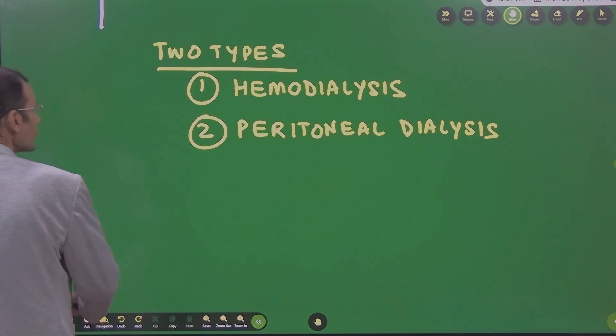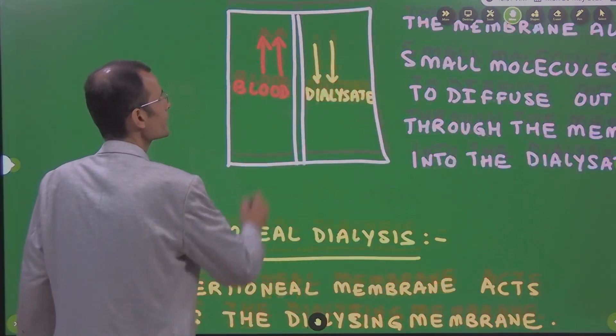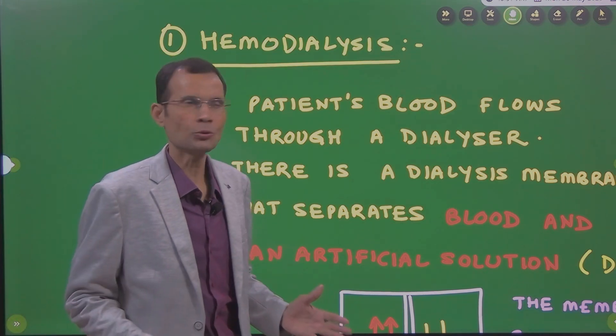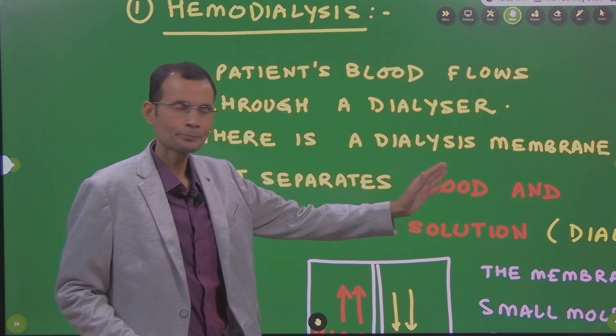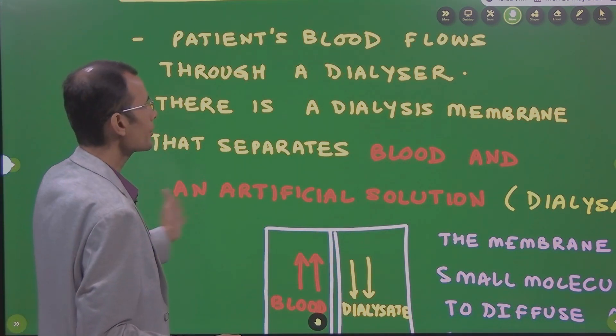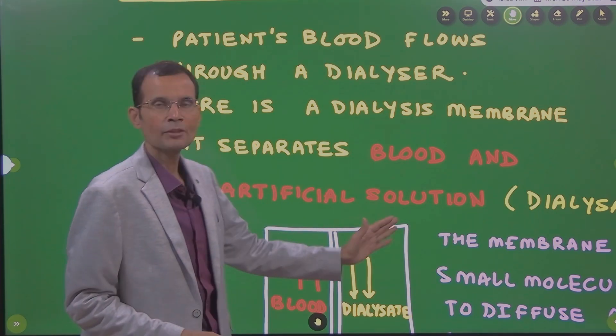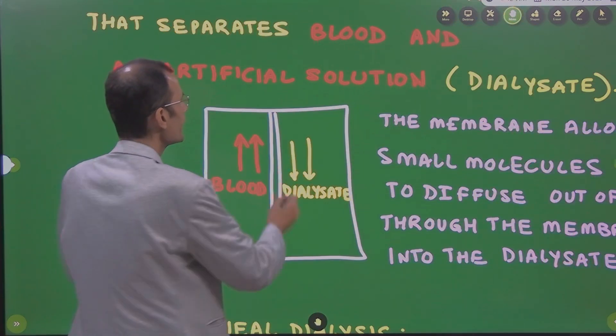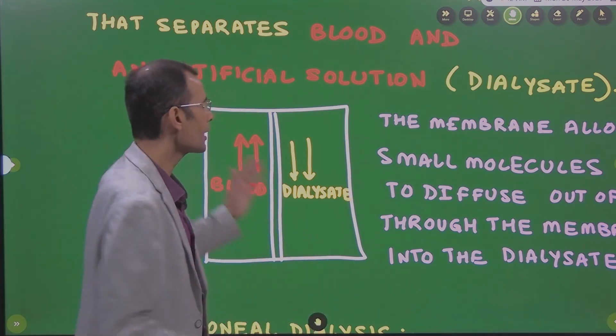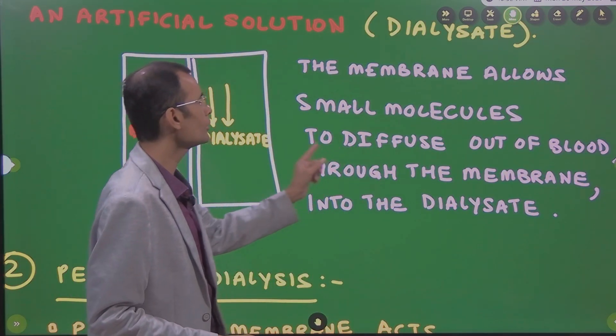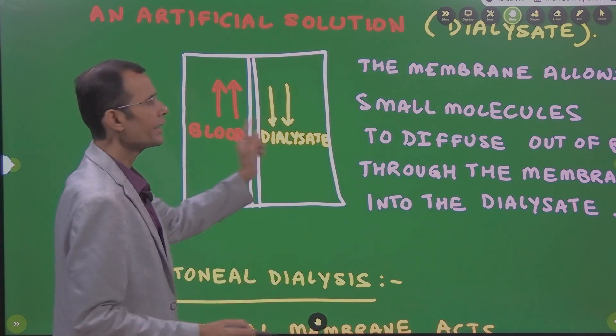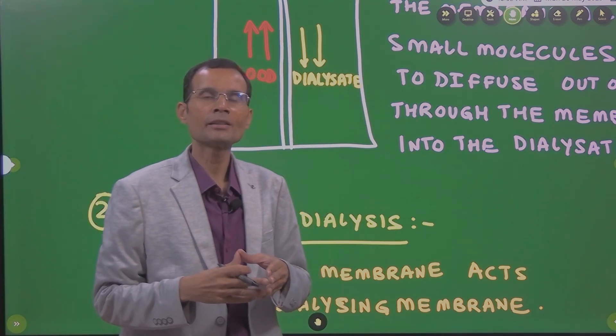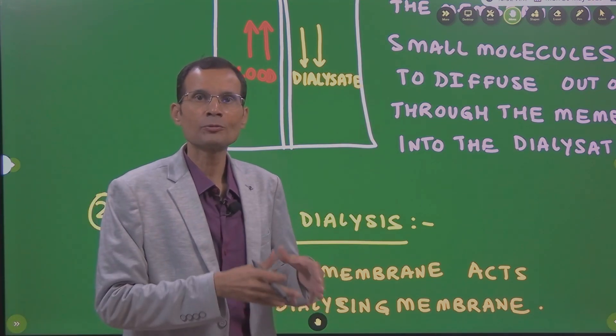Although they perform the same function, the procedure differs slightly. In hemodialysis — hemo meaning blood — the patient's blood flows through the dialyzer. There is a dialysis membrane that separates the blood and an artificial solution. As you can see, blood flows through the machine and the dialysate flows through it as well, separated by a selectively permeable membrane. The membrane allows small molecules to diffuse out of the blood through the membrane into the dialysate, separating the substances to be eliminated from those to be retained in the blood.